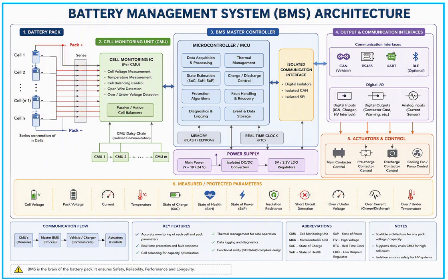Its major responsibilities include data acquisition, collecting cell voltages, pack voltage, current, temperature and fault information from all CMUs, and state estimations such as state of charge, which indicates the remaining battery capacity, state of health, which represents battery aging and remaining useful life, and state of power, which determines the maximum power the battery can safely deliver or accept under current operating conditions.